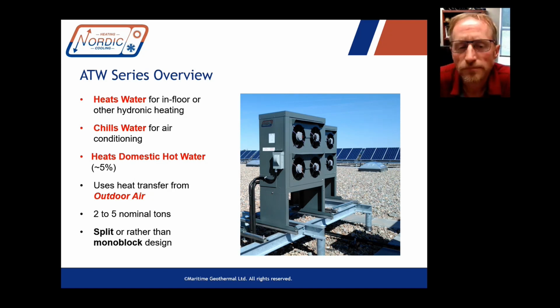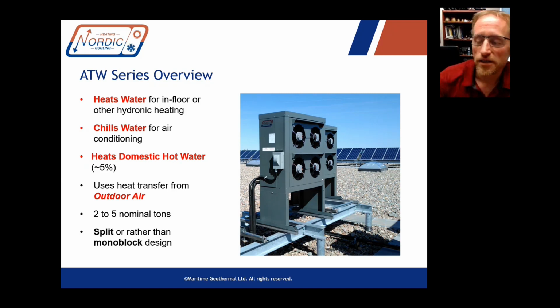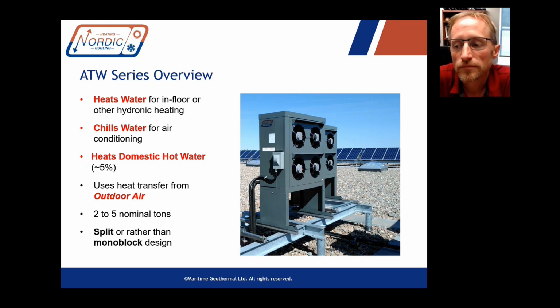Okay, so that's basically the interface between this system and your hot water system, essentially. Right, and one more thing to mention there is that if the domestic water gets all the way to 140, there's a temperature switch to turn off the circulation pump that's built into the desuperheater in the heat pump, so it'll stop heating water in practice at maybe 140, 145 Fahrenheit, something like this. Okay, and this is all just taking about 5% of the capacity of the system to do this. Yeah, and in heating mode, you're getting the same COP heating domestic water as the main output, of course, and in cooling mode, you're actually taking heat out of the space and putting it in the domestic water tank, so that's free. So whatever water heating it does during cooling mode is actually heat that's been removed from your living space. So it's kind of neat.